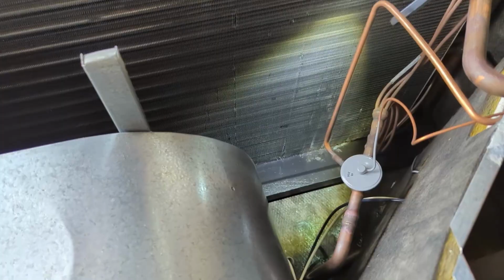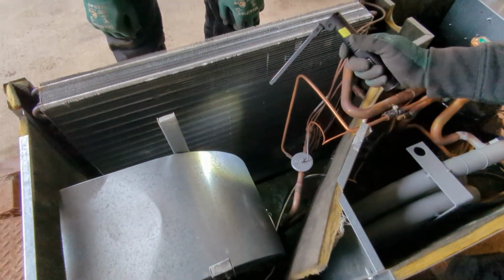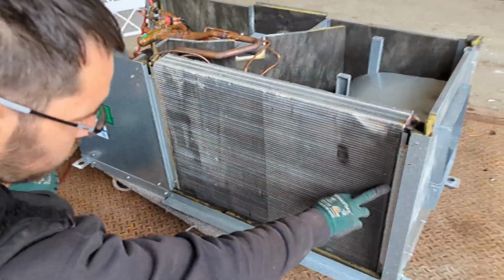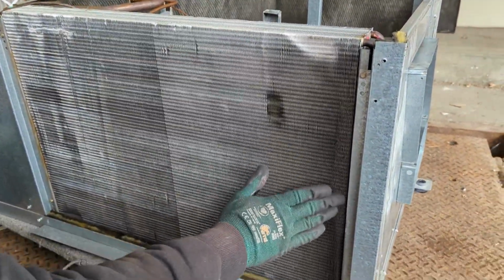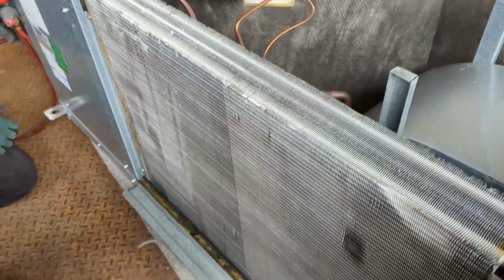So, got her all disconnected, took her down, took her outside, and this time we were looking for a refrigerant leak. When we opened the lid of this unit, we kind of use all of our senses in HVAC. We saw a lot of oil residue on the evaporator coil, so that's where we focused our efforts. We were checking for leaks all over that evaporator coil.